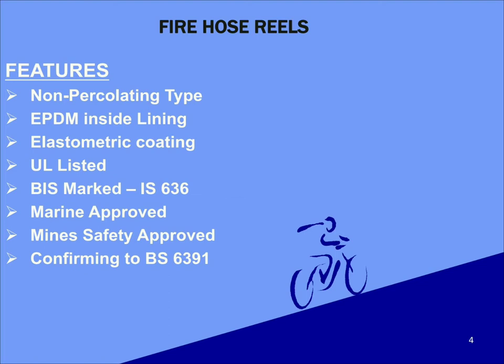EPDM exhibits outstanding resistance to heat, ozone, steam and weather. It is an electrical insulator. Type 2 hoses have got an elastomeric coating on the outer side; this coating is approximately 10 times thicker than paint, forming an incredibly thick yet flexible coating that helps the exterior to be waterproof. Fire hoses also carry the following international certifications: UL listed, BIS marked IS636, Marine approved, Mine safety approved, and conforming to BS6391 standards.